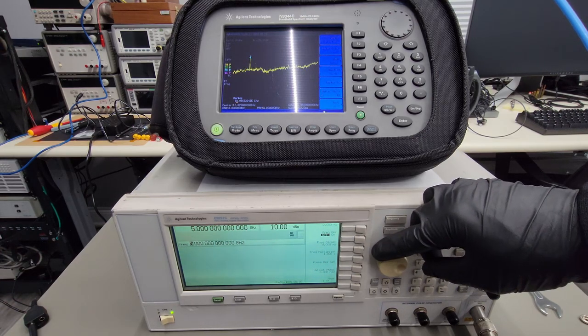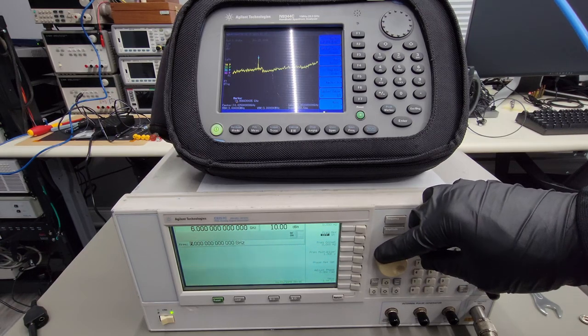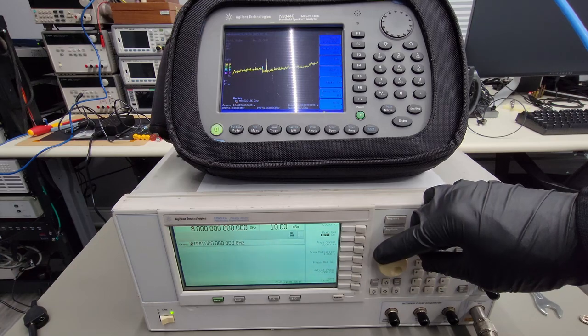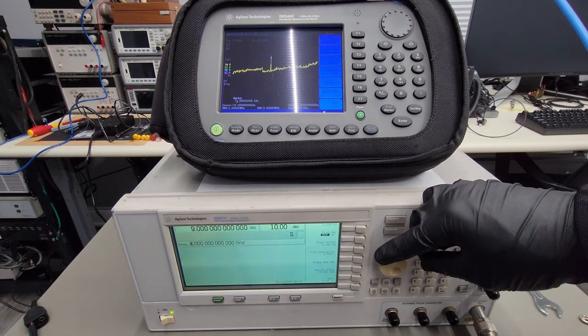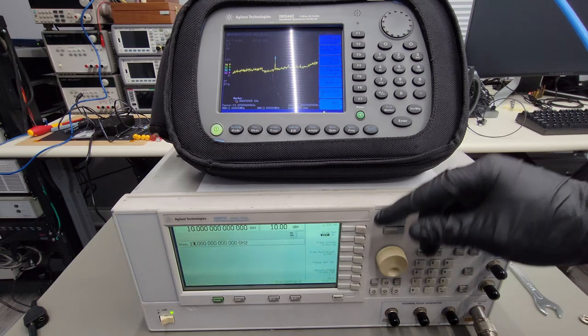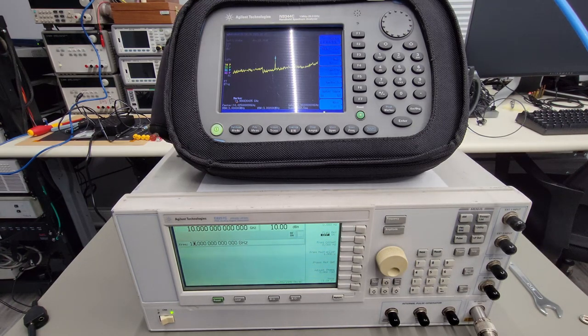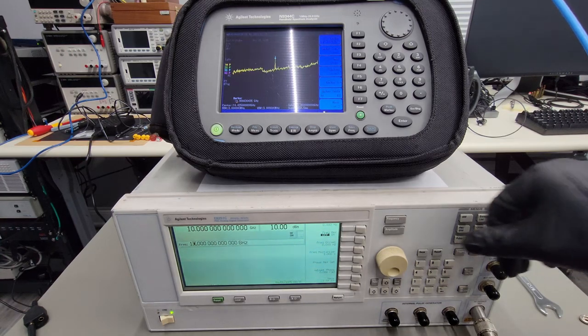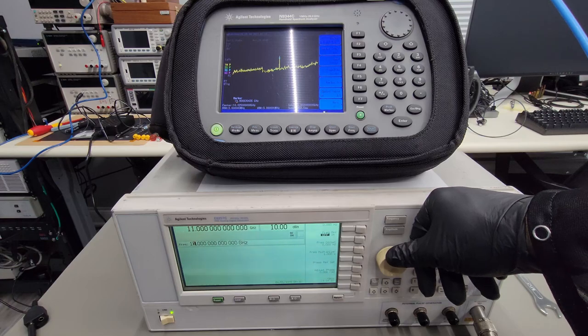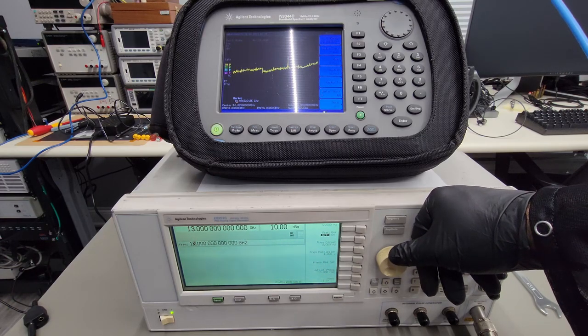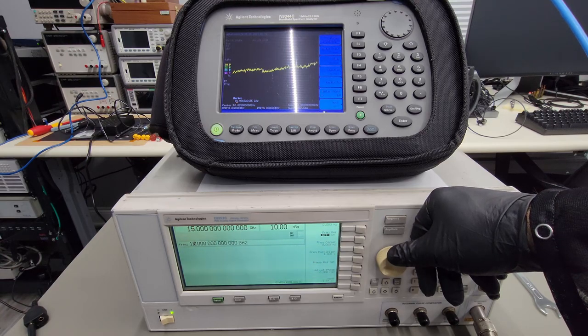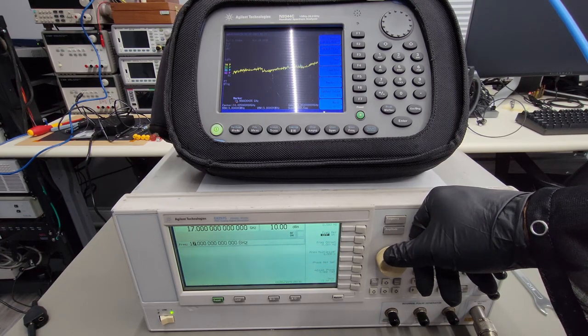But we appear to have frequencies, at least in the low band so far, 6 gigahertz, 7, 8, 9, 10, still around minus 20 to 23 dBm. And, you know, of course, we're going to have a little bit of loss in the cables and adapters, even though these are pretty good. The adapters are rated up to 18 gig, and the cable is rated up to 26.5 gig. So we are going to lose a little bit of power in our cables and adapters, but it does seem like the power is relatively flat. Keep going up in frequency here. 16, 17, 18, 19, 20.